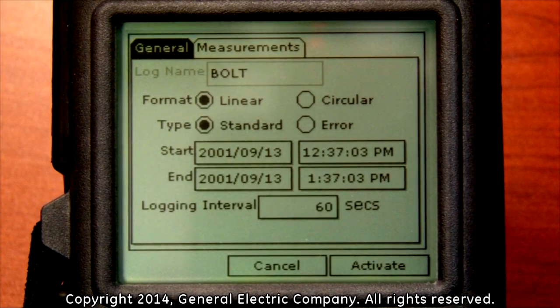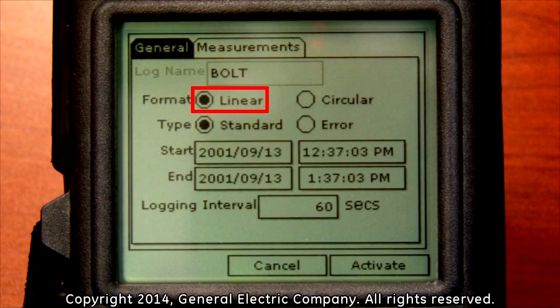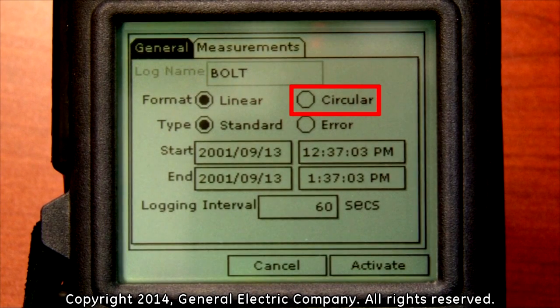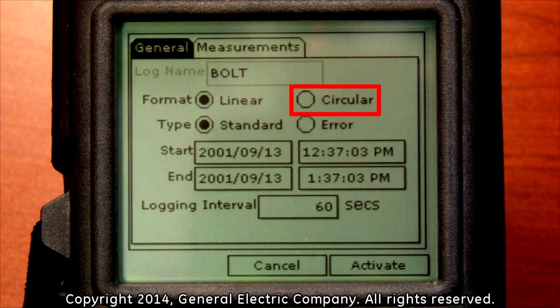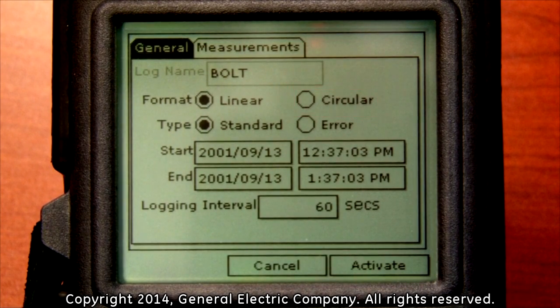Under the general tab you will need to choose which type of log format you will use. A linear log is for starting and stopping data logging, taking measurement recordings at specific times and specific intervals — this format is a discrete logging program function. A circular log is for starting data logging at a specific time, recording at specific intervals until a designated number of records are reached, then recirculating back to start over — this is a continuous logging program function. For this example we will choose a linear format with the standard type option.